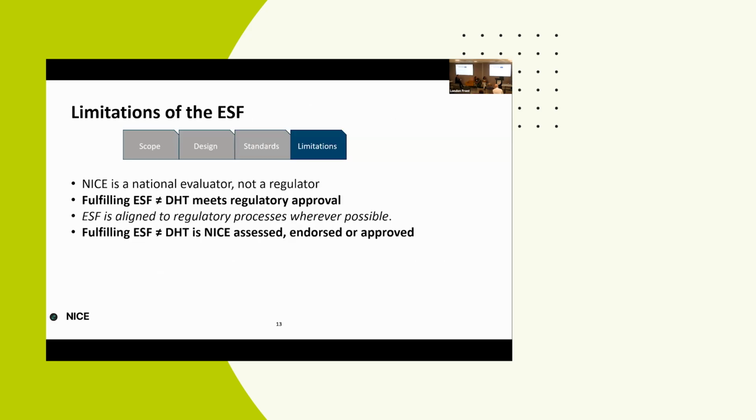Now, some of the limitations of the ESF. NICE is a national evaluator. It's not a regulator. So fulfilling the evidence standards framework does not mean the product meets regulatory requirements. That's the MHRA's role. We have aligned this as much as we can to MDR and the plans for what the future medical device regulations might look like. So it's important to acknowledge that.